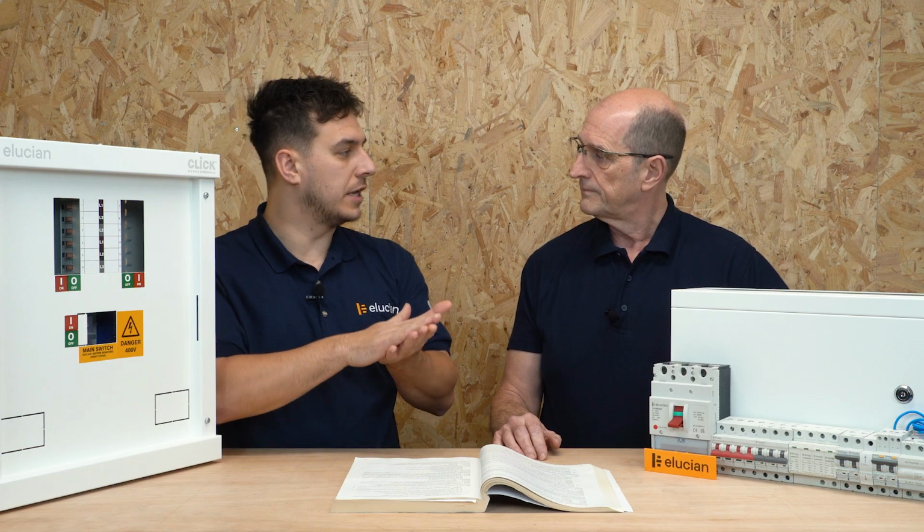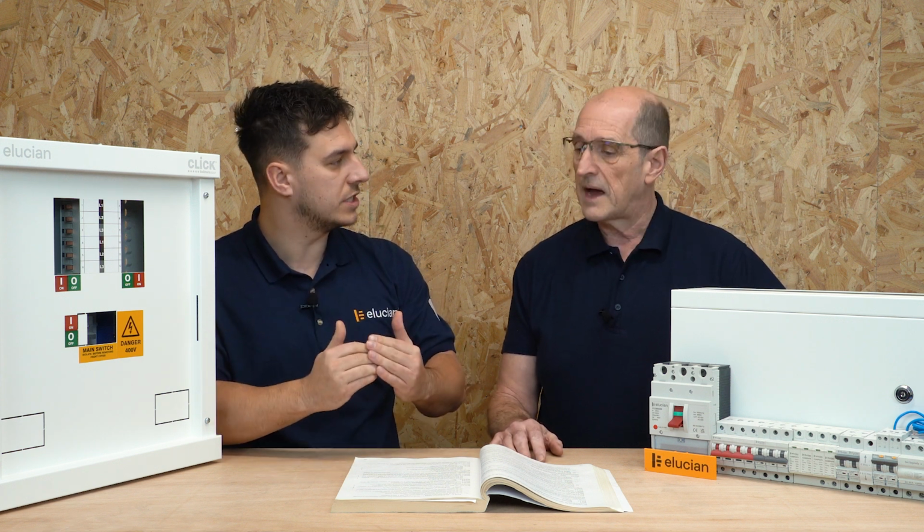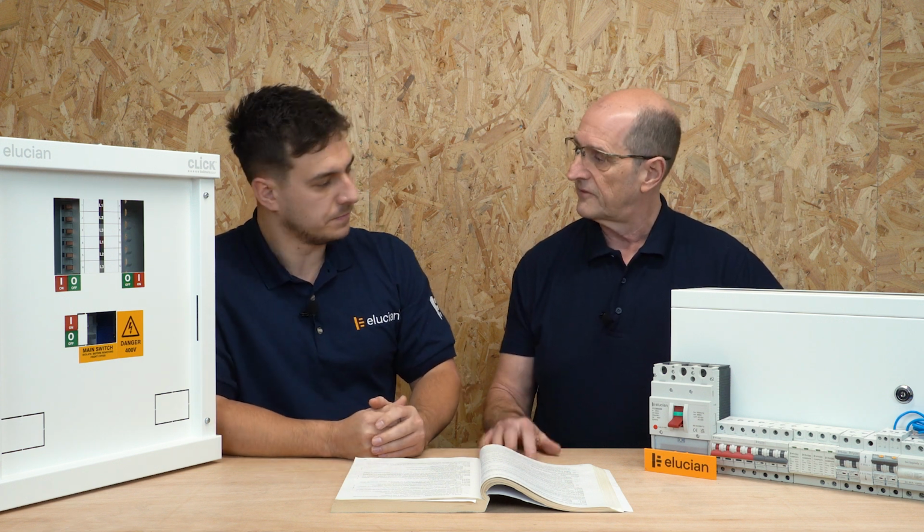Yeah, I think that's what I was getting to. If, let's say, the manufacturing instructions stated that it needed to be a Type F, and certain manufacturers didn't produce them, well, actually, we could increase the level and go to a Type B. That way, it's always going to be the one below. Absolutely. You could select a Type B instead of a Type F.